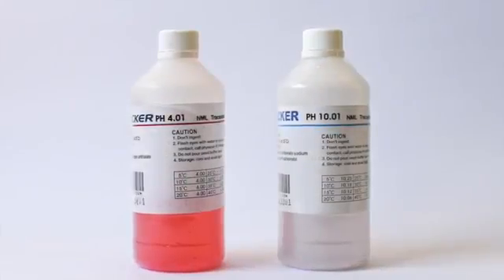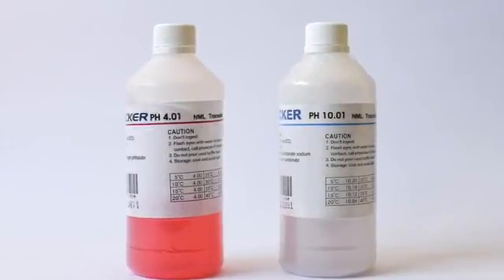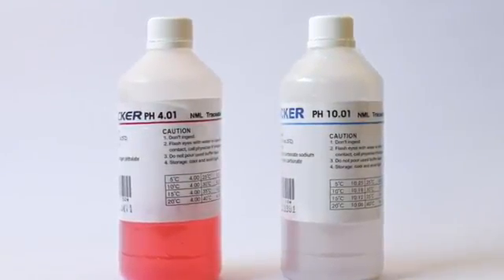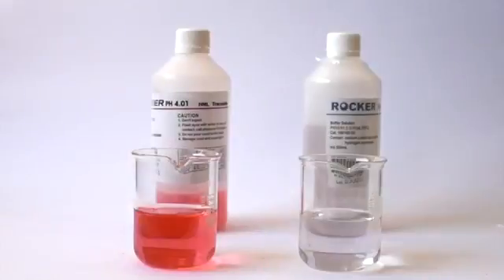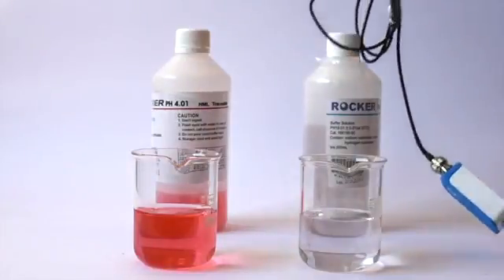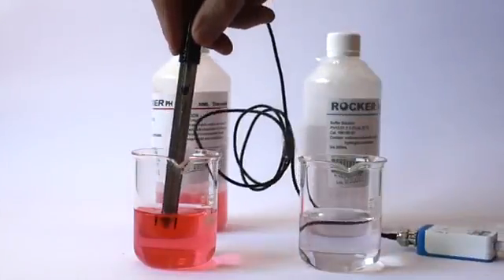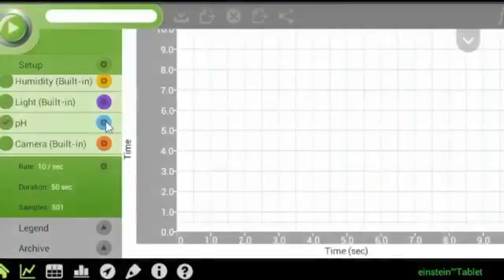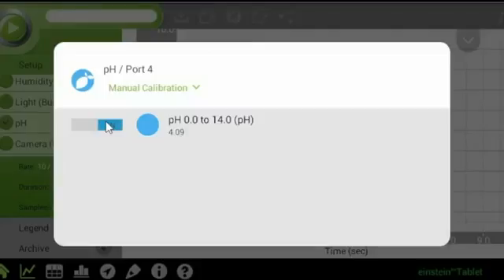First, we will need 2 different standards. In this case, 2 solutions whose pH level we already know. Here we have 2 buffer solutions, one with a pH of 4 and one with a pH of 10. Insert the pH electrode in a container of pH 4 buffer. First tap the setup button, then tap manual calibration.